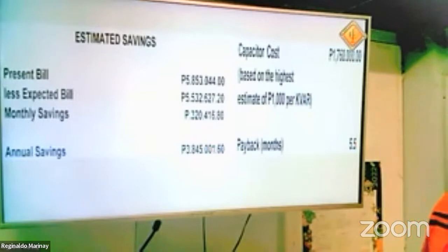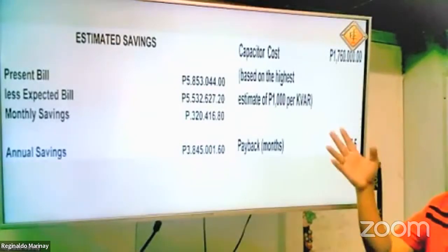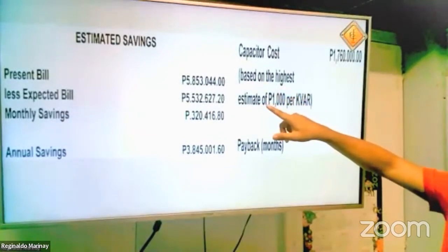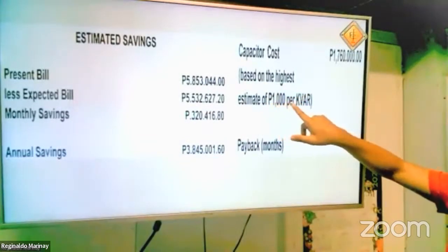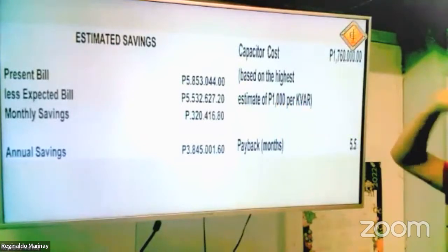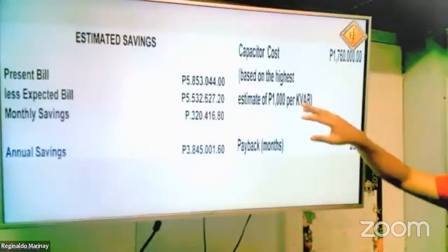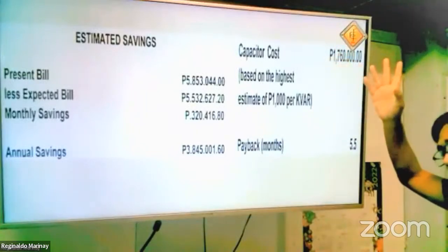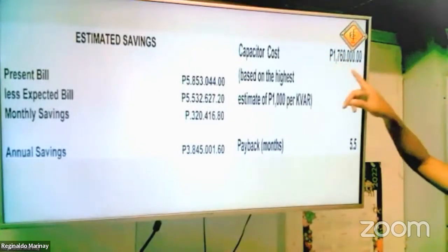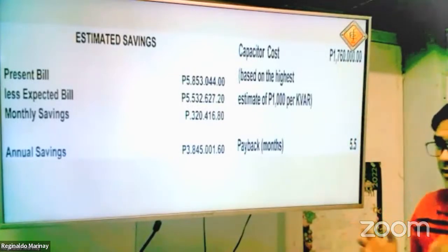Let us say, conservatively, during this time, although not updated, based on the highest estimate of 1,000 pesos per kVAR, or simply 1 peso per VAR, let's say your calculated value is a 1,760 kVAR capacitor. So whatever the value, from the formula I've shown you, take a look here, partner.